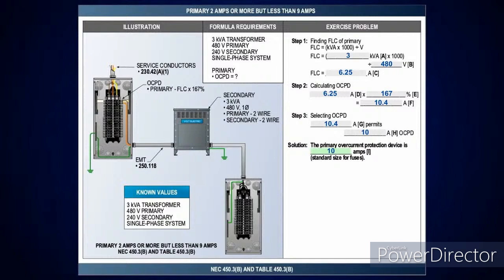So I've got a 3 kVA transformer times 1,000 is 3,000 VA. I'm going to divide that by 480 volts, which is going to give me 6.25 amps. Then I'll multiply that by 167%, which gives me 10.4. I can't exceed that calculated load, so I have to drop down. I go look at table 240.6A. The next size below that is 10 amps.